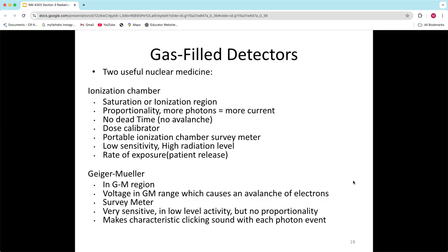So it can see it's low. I said that backwards, sorry. It's low sensitivity, meaning that it's not sensitive, so that it can do a high dose. So if you're measuring your I-131 patient, they have a lot of dose coming off them, and so it's going to be less sensitive so that it can see that high amount. If it was super, super sensitive, that high amount would just overwhelm the system, okay?